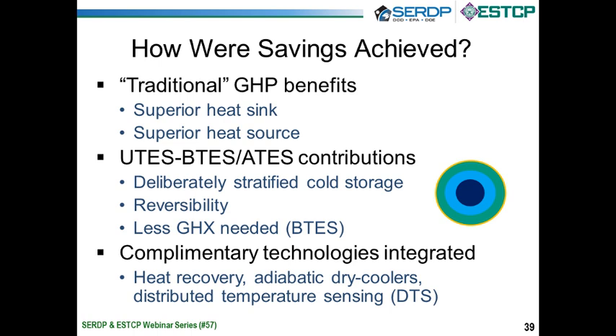Now, the thing you've got to watch is the heat recovery load, the cooling load and the heating load never balance, and the heat pump doesn't care. It can really do one or the other, but it can't do both. And so we had 10 steps of capacity control because we had five modules, each with two independent refrigeration units. We may even retrofit these units at Albany, one of the compressors with a VFD on there, so we can tune it to exactly the load. But the BTES, the ground loop, is what gives you some thermal mass so that maybe you're not banging these systems on and off so quickly. So anyway, a few tricks there you've got to be careful on, but heat recovery is a technology I really like.